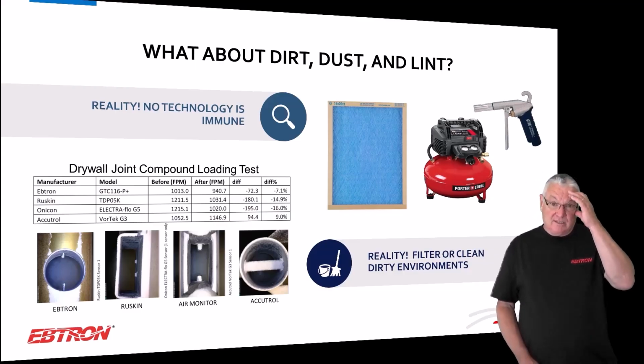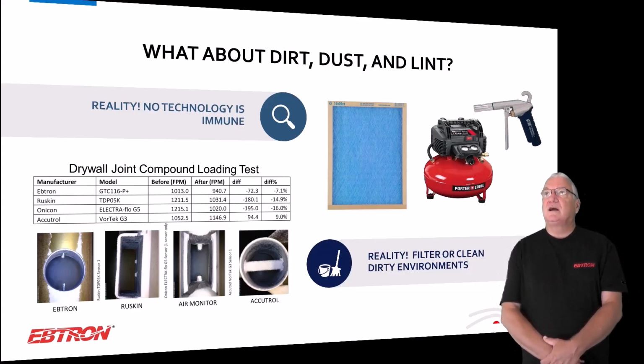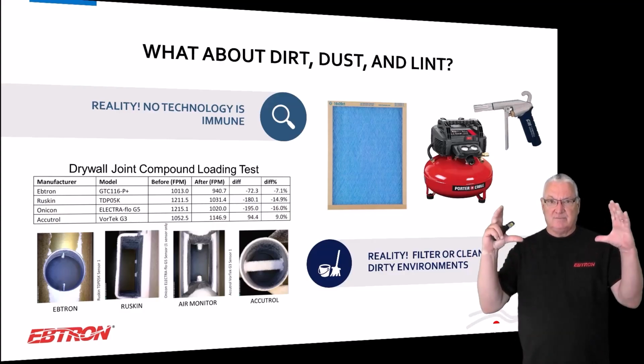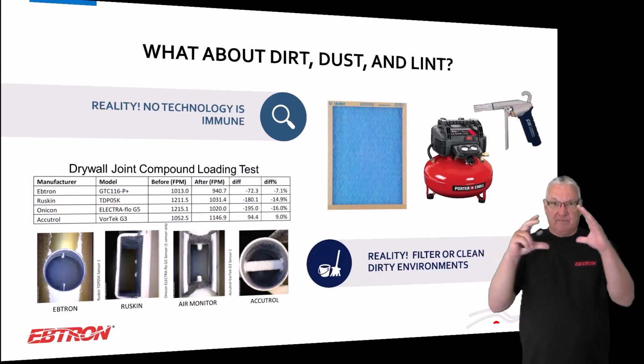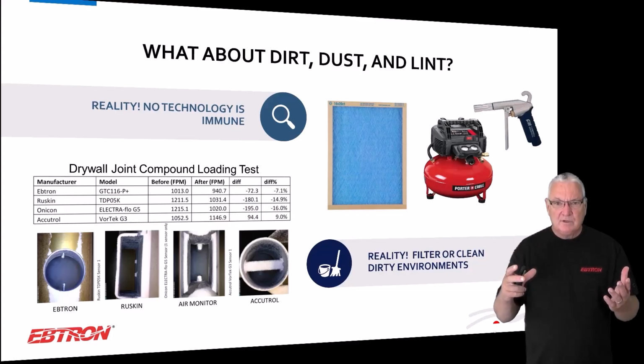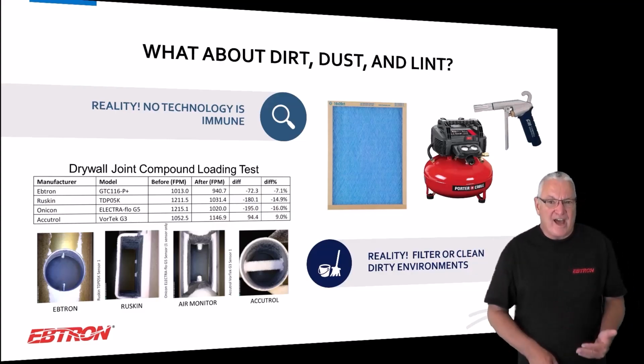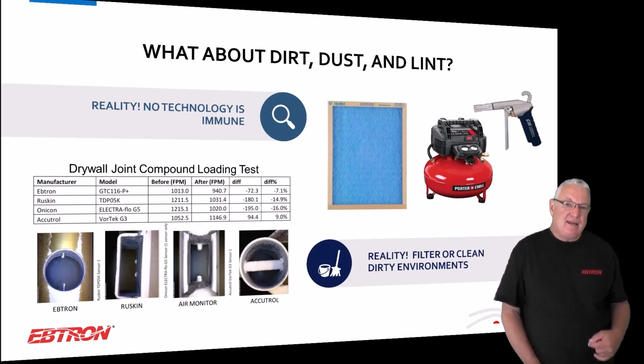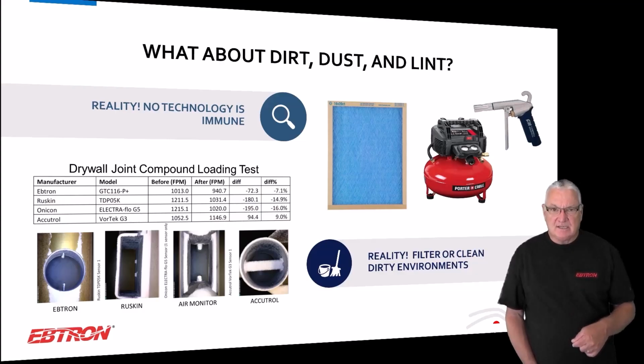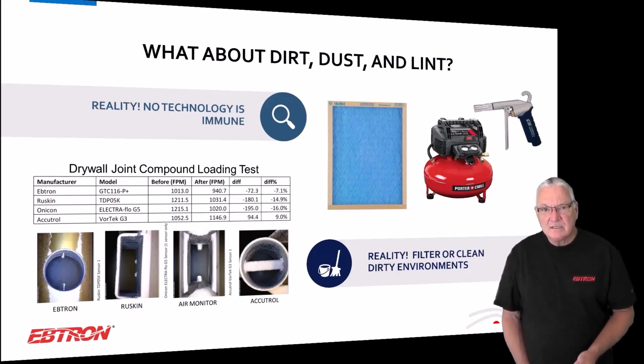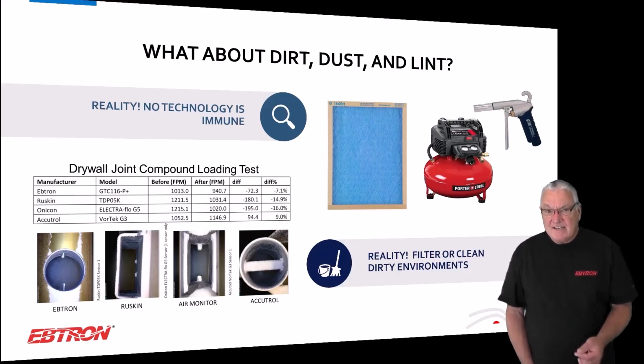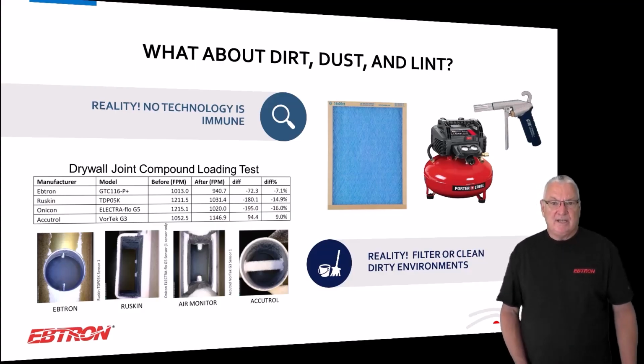I mean, I'm going on a little tangent here. I've seen compounding pharmacies with ducts this big that after a period of time, the inside of the duct is this big. That's a problem, okay? You don't want that, all right? And the general term lint is not necessarily what it is. It's lint, it's binders, it's cleaners, it's dead skin cells. I mean, think about it, it's dead skin cells. Do you want dead skin cells in the return duct on the other side of the grill in an OR? It's ridiculous to me.